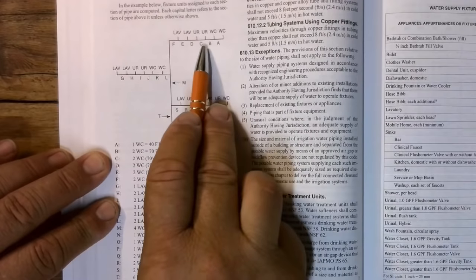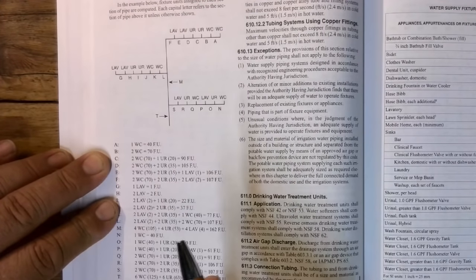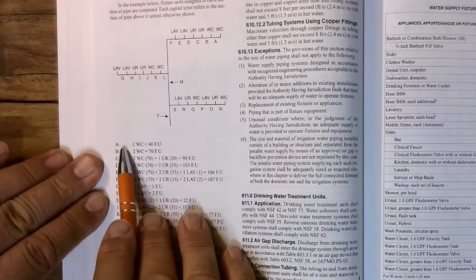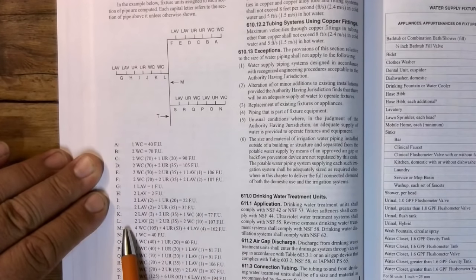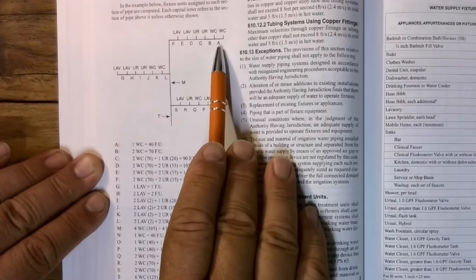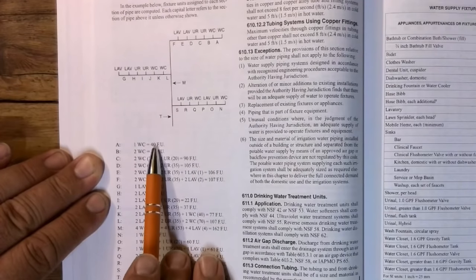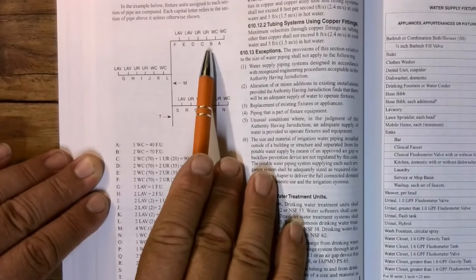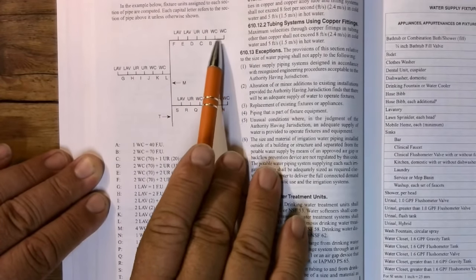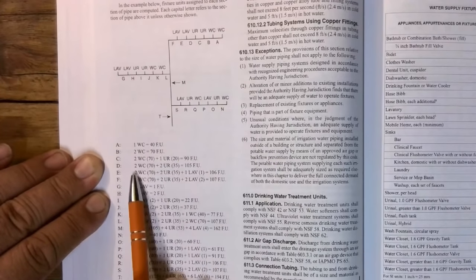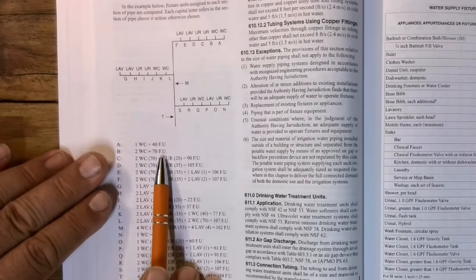Up here, A, B, C, D, E, F, right? So they want to know what your fixture unit values are for each one of these letters. Since A only has one fixture, one water closet, that's 40 fixture units. B has two water closets on it. See, it's got two water closets there. So you have two water closets, 70 fixture units.